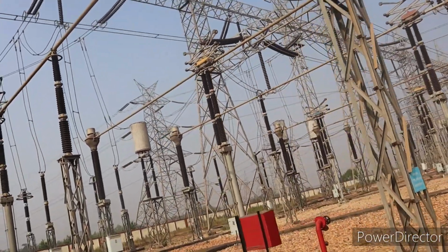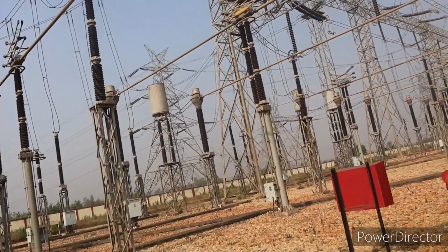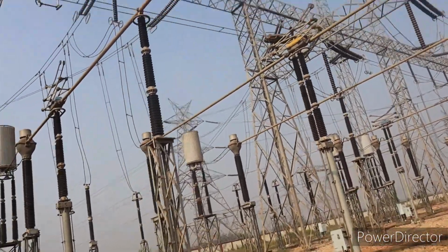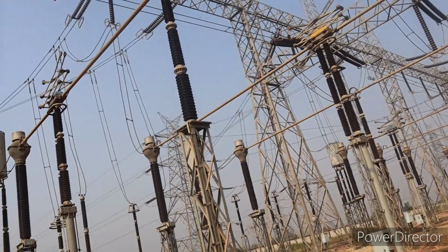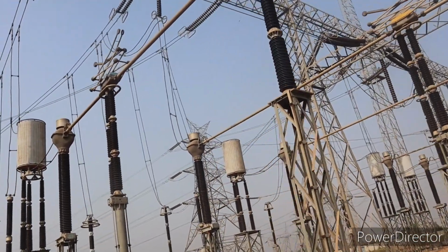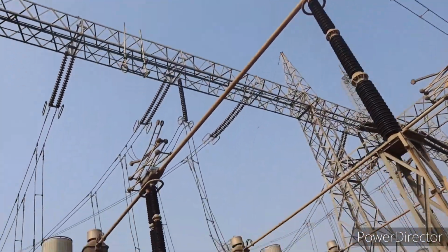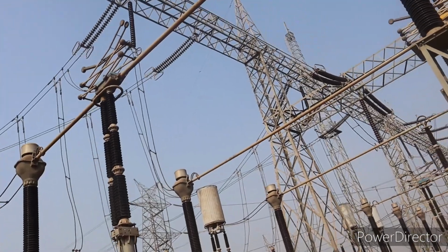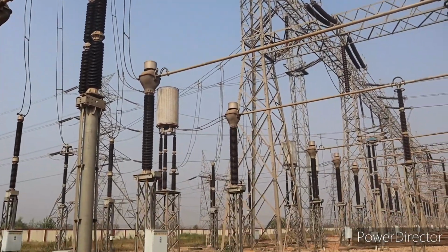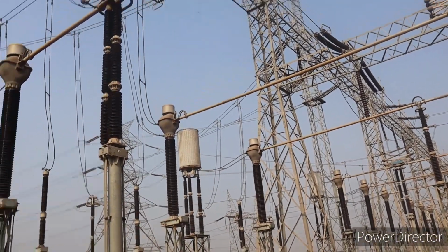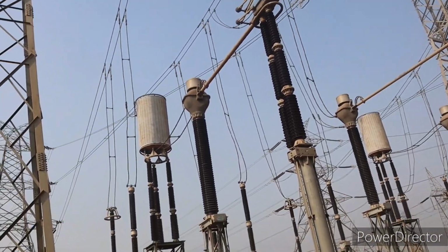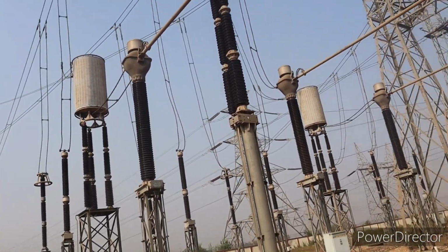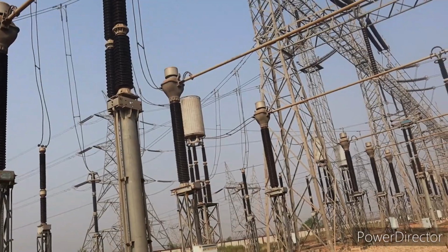This is the bus support, and this is the transfer bus isolator. Transfer bus has twin moose conductor used. The transfer bus isolator is also a pantograph type isolator, and now it is in open position. That means the circuit is not diverted through the transfer bus.